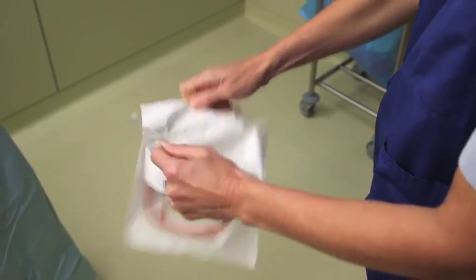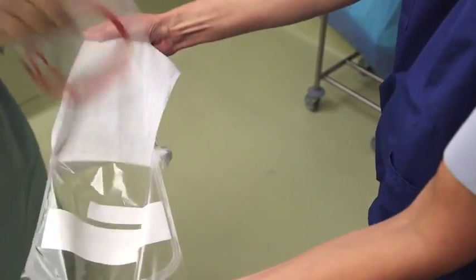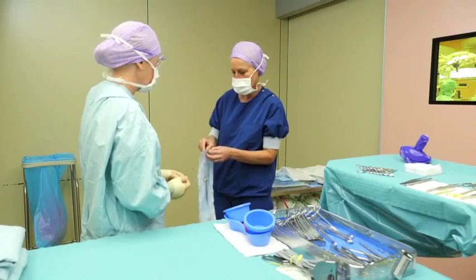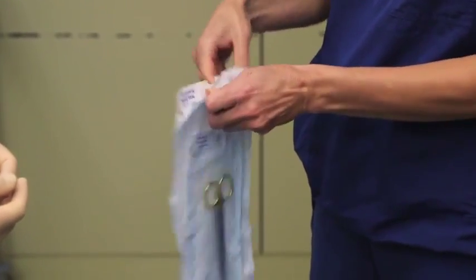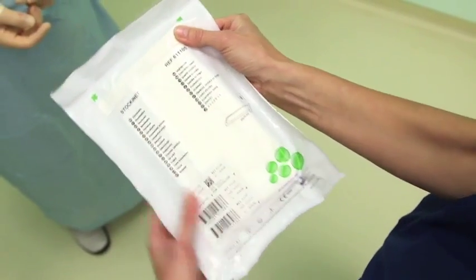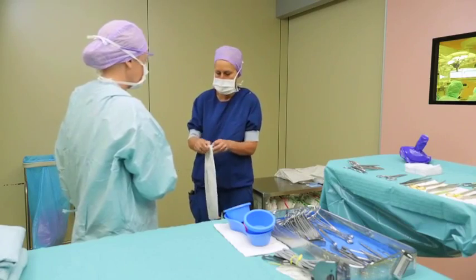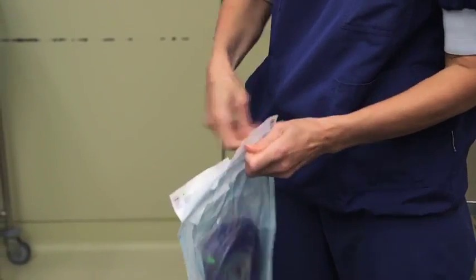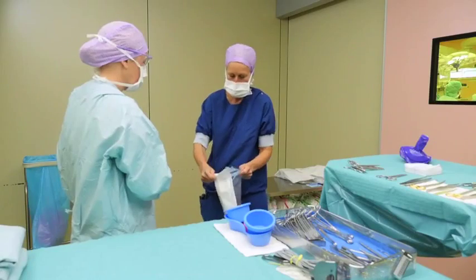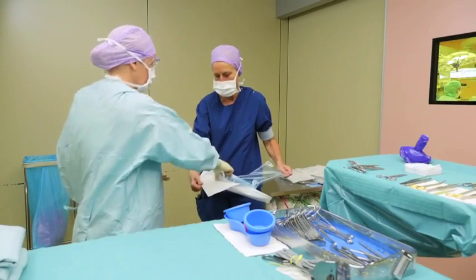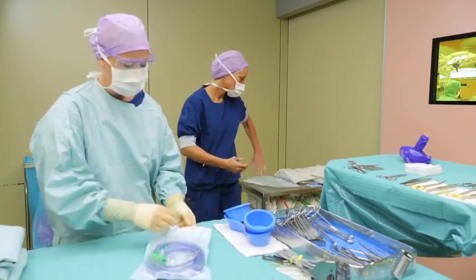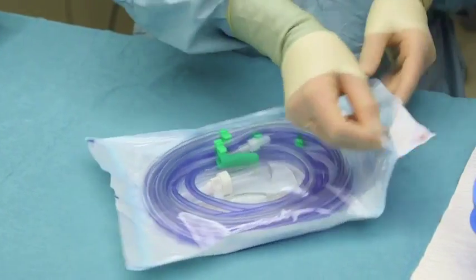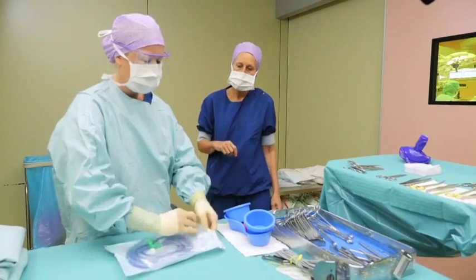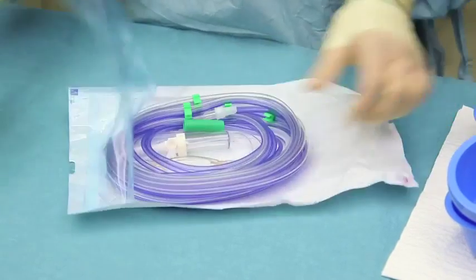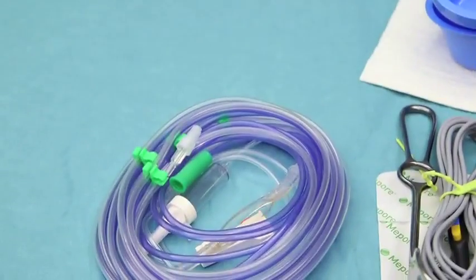The seals of the packs should be peeled slowly and evenly, starting at the specified position, depending on the design of the sterile barrier system. This is usually at the chevron end, or may be indicated with arrows. For large packs, the best approach is often to start peeling first on both edges, so that the last peeling is the middle of the seal. You should respect the direction of peel indicated by a peel symbol. Minimize the creation of fibers and particles without tearing or delamination. Bursting or tearing the barrier system will result in a high risk of contamination.